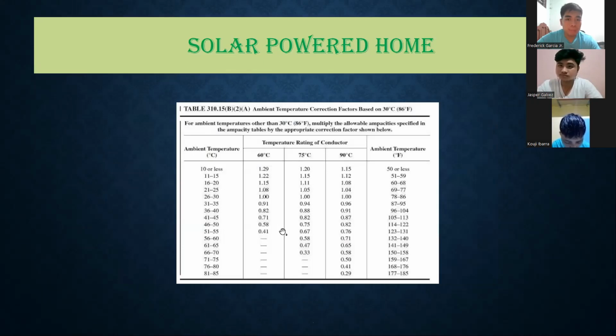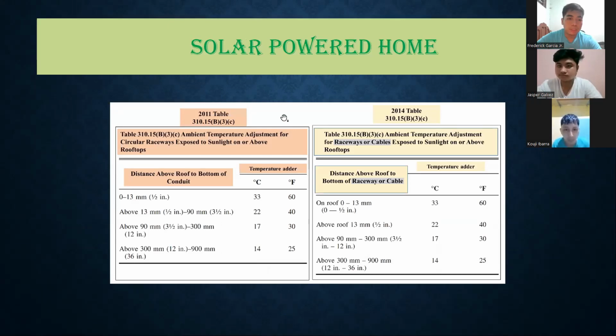Now we have the ambient temperature correction factors based on 30 degrees. Now if our environment is not 30 degrees, greater or below 30 degrees, we'll be using correction factors present in this table. We'll also be using it later since the ambient temperature of the Philippines is 37 degrees Celsius. Here we have another table for the ambient temperature adjustment for circular raceways exposed to sunlight on or above rooftops.